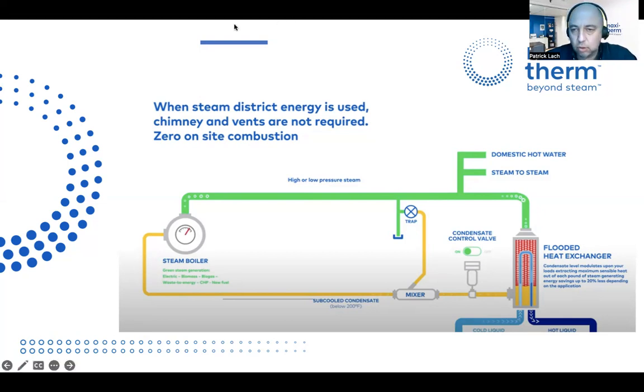And while we do so, we can dump condensate under 130 Fahrenheit during all operation, which means no fresh water needed. As you can see on this, the control valve is on the condensate. So when the valve is modulating, we're playing with the heat surface area, and the condensate level will vary during all operation. No water hammer, no banging, no such thing. It's a very, very smooth operation. And the only moving part is a half-inch control valve up to 10 million BTU. So easy fix, very low maintenance.